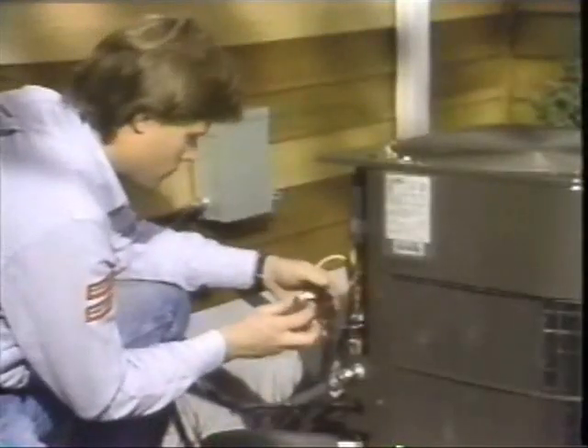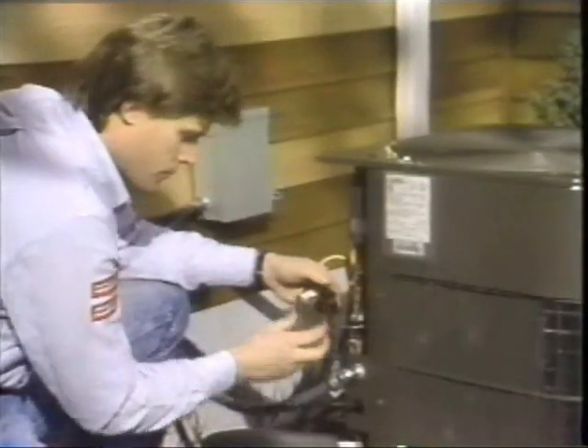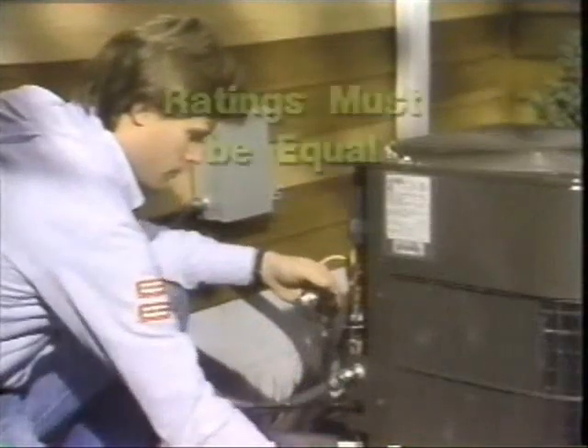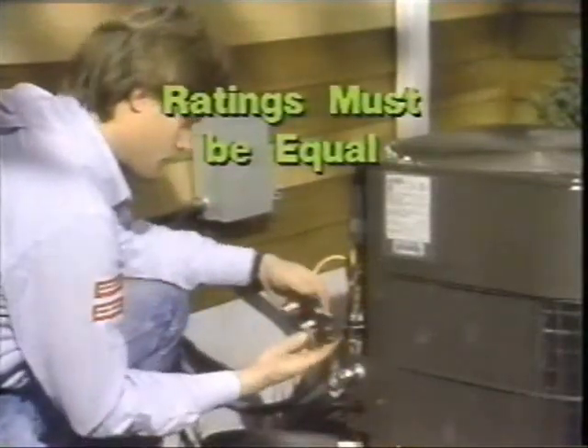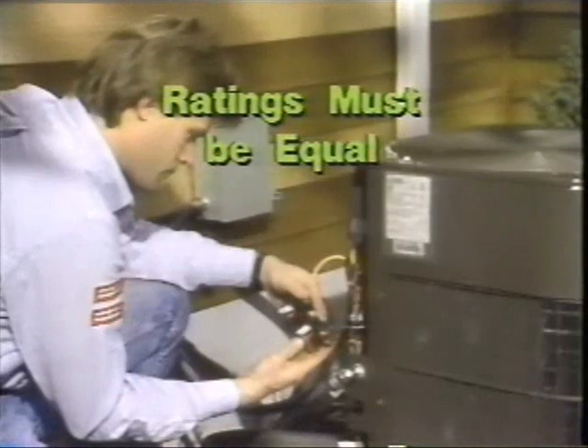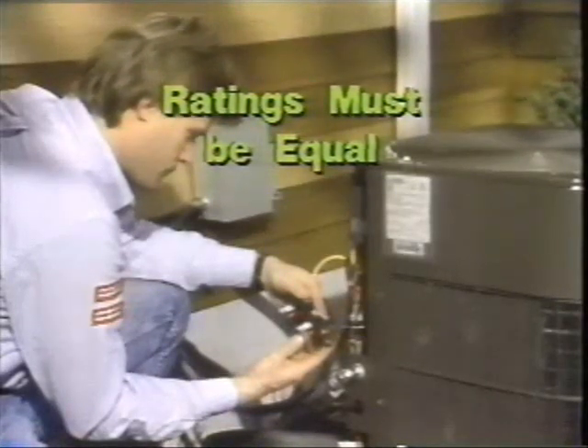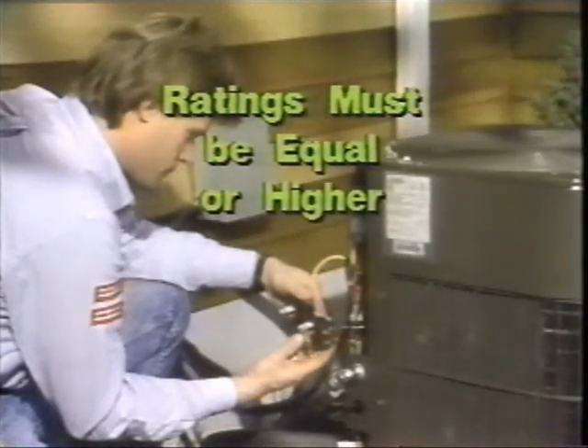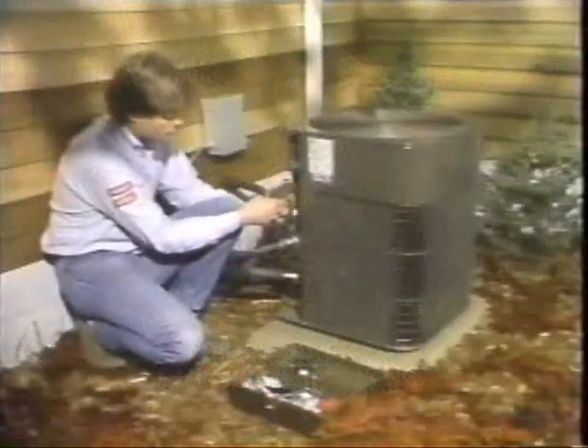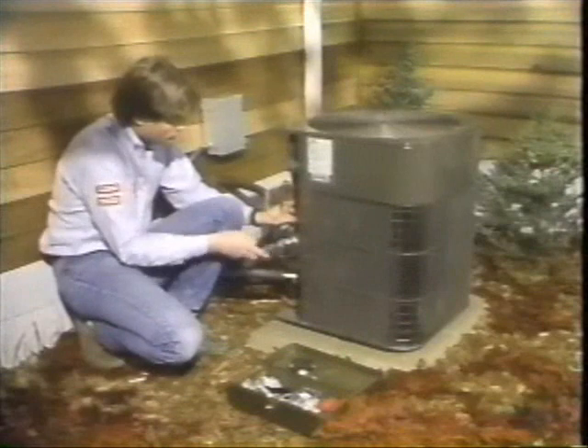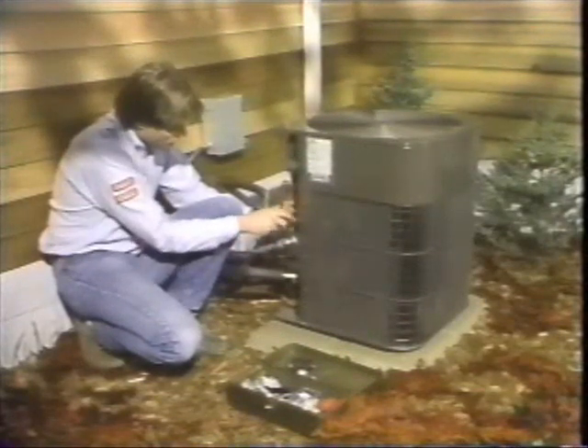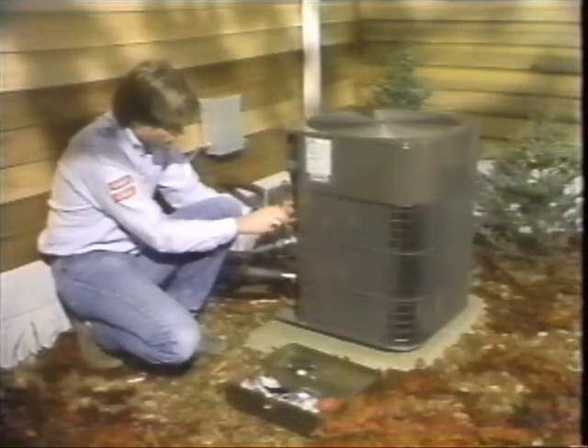When replacing a contactor, compare its contact rating with that of the replacement. The new contactor ratings must at least equal the old contactor. And by using a replacement with a somewhat higher contact rating, you buy extra reliability and service life. And of course, you need to compare the physical size of the old and replacement contactors to ensure that the replacement contactor fits. If you determine that the contacts are bad, remember that you have the option of replacing just the contact.